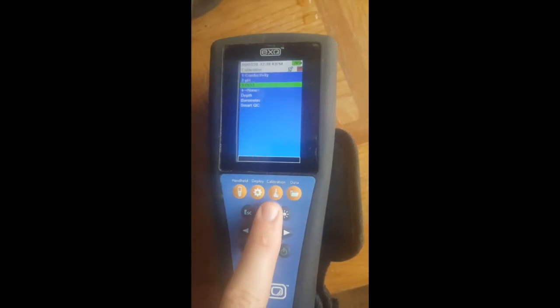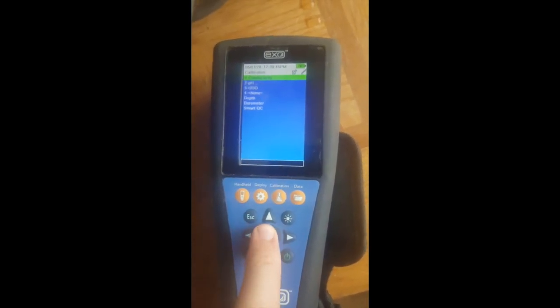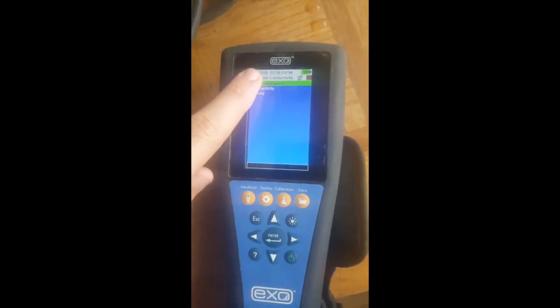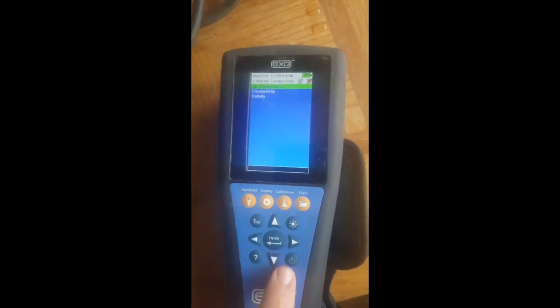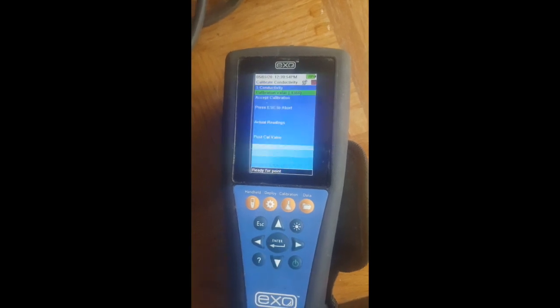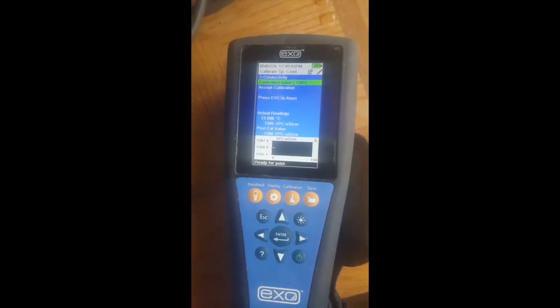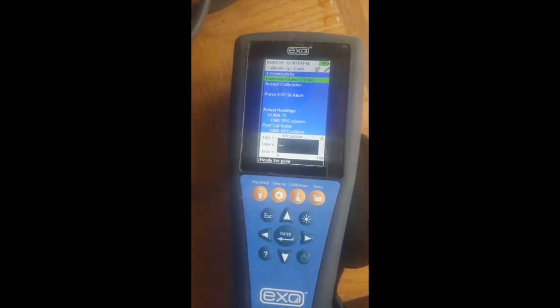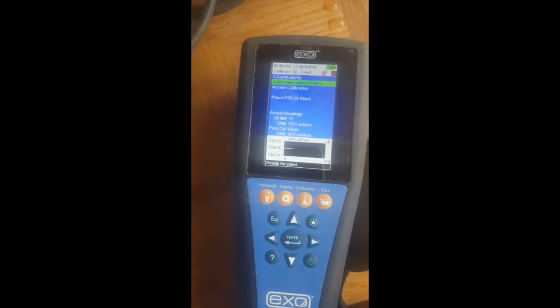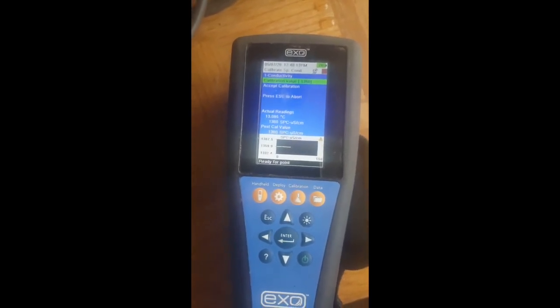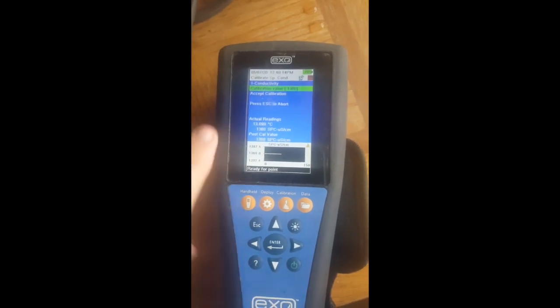For calibrating conductivity, we're going to go with calibration, conductivity. We want to calibrate. We always select specific conductivity. On your bottles, you'll have a standard value on your conductivity. We get our conductivity solution from the South Dakota Health Lab, and they put a standard value of 1410 on here. So we're going to adjust our calibration value to 1410.